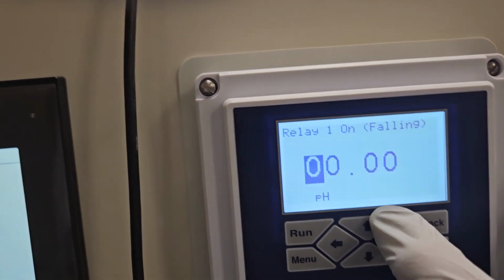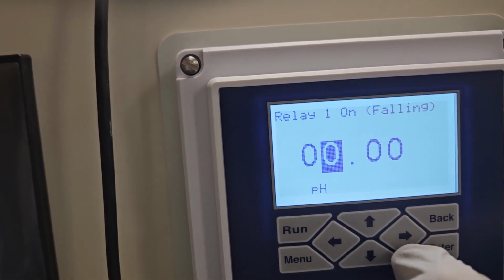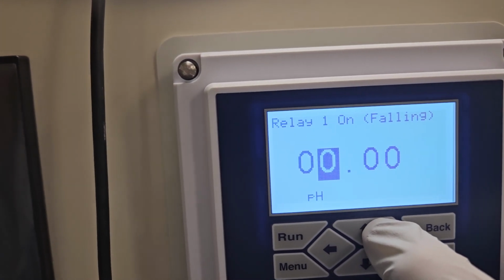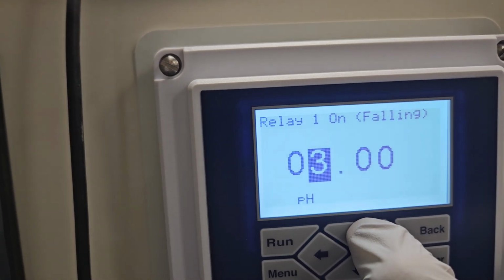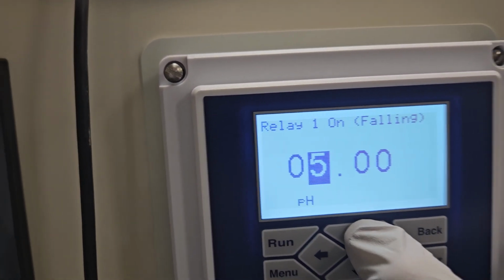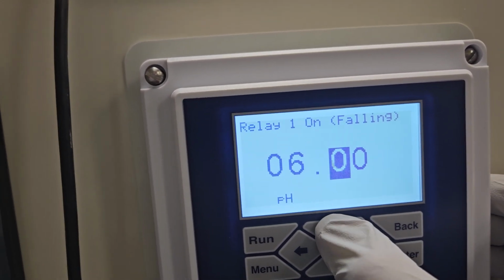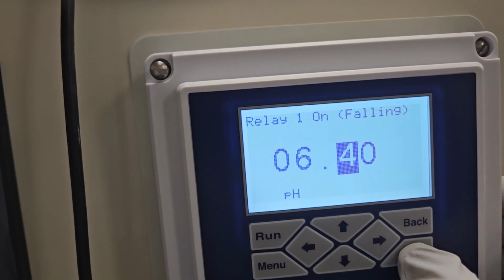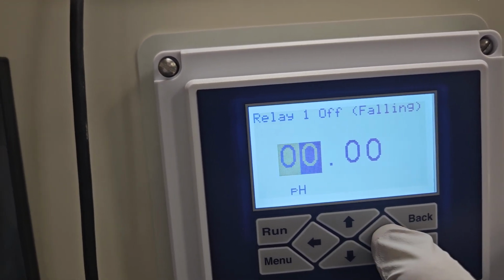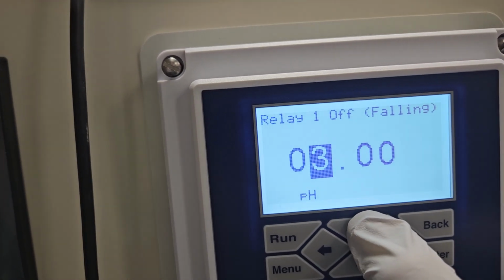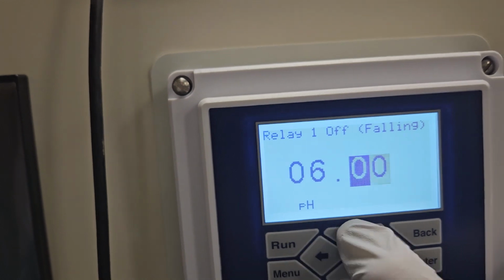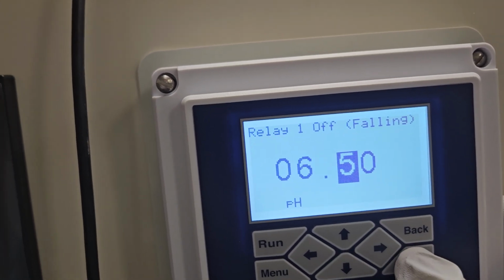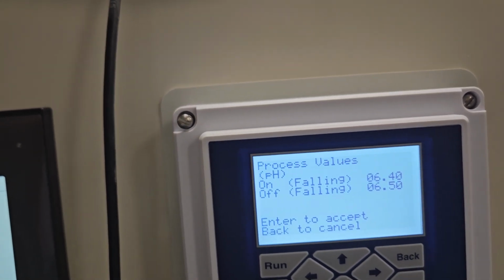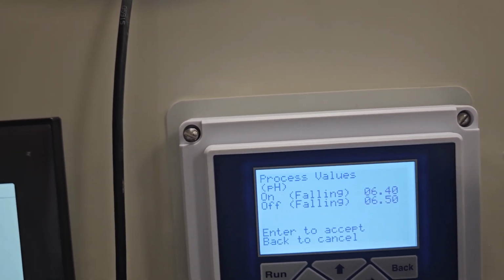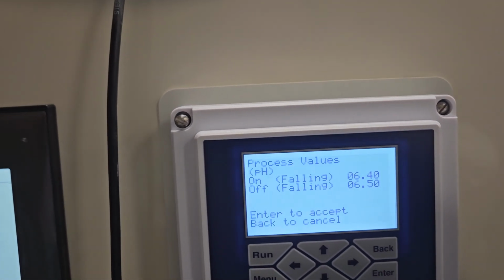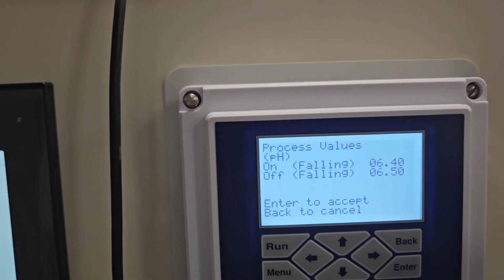And then you put an on point, so you can move the cursor over here and select. So let's say we'll have it on at 6.3 or something, or 6.4, 6.4, and we're going to turn relay 1 off at 6.5. So it's going to add, in this particular one, up to 6.5. If you want to use different points, you can use different points. So now this process the relay will always be on at 6.4 and below, and once it reaches 6.5, it turns off to stop adding caustic or lime or something of alkaline nature.